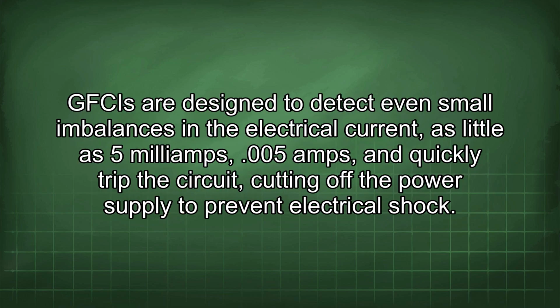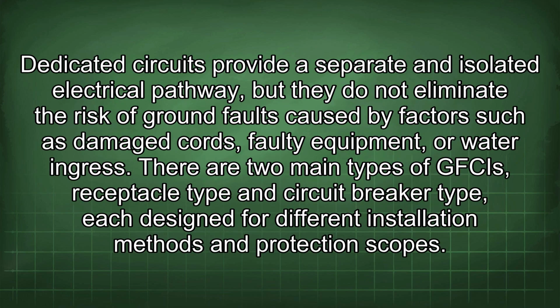GFCIs are designed to detect even small imbalances in the electrical current, as little as 5 mA, and quickly trip the circuit, cutting off the power supply to prevent electrical shock. Dedicated circuits provide a separate and isolated electrical pathway, but they do not eliminate the risk of ground faults caused by factors such as damaged cords, faulty equipment, or water ingress.